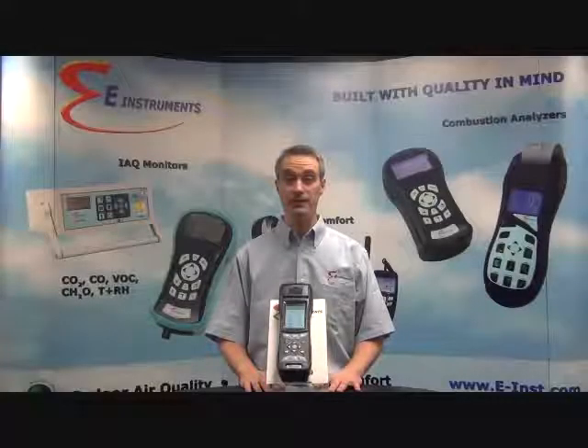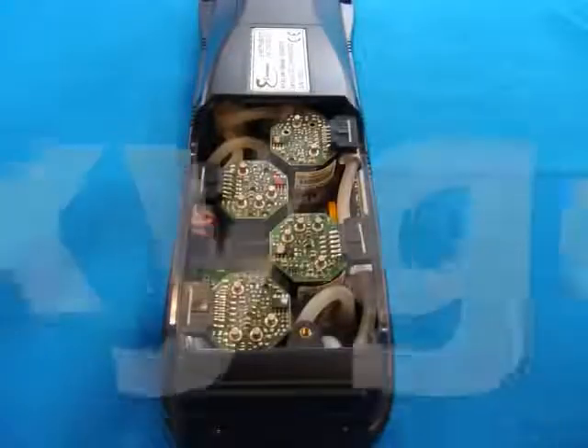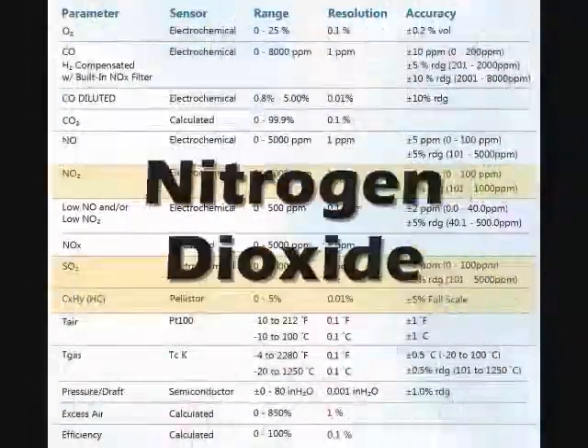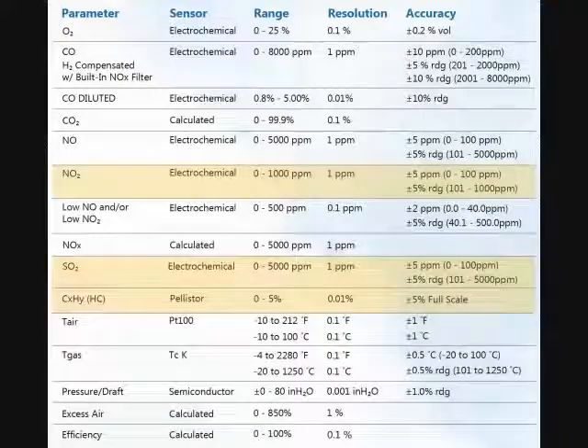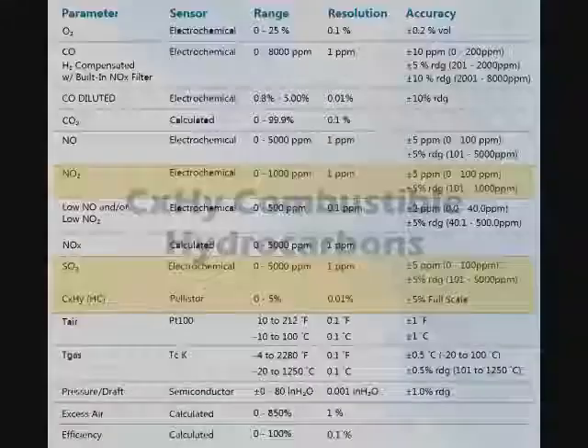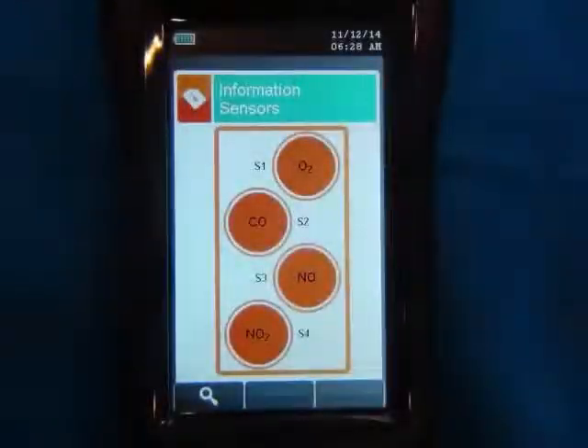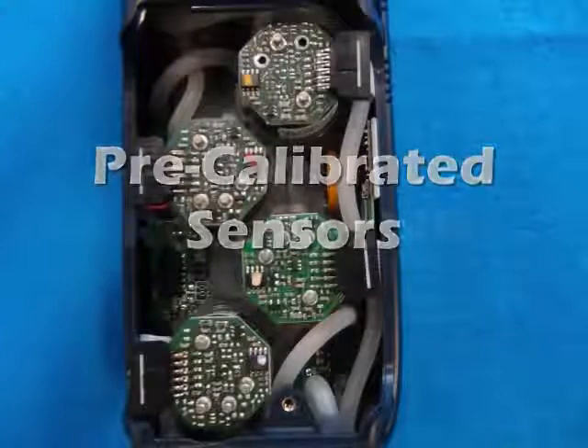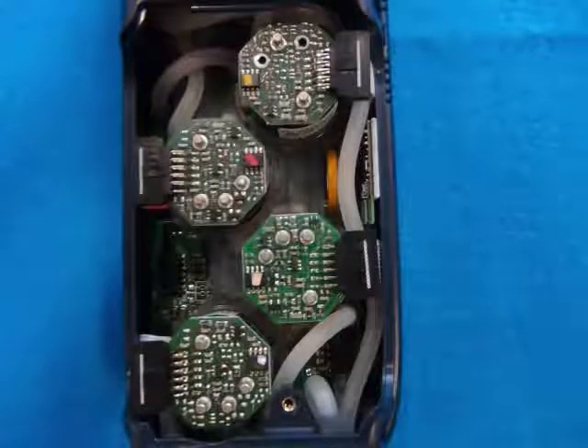The E-4500 can be configured to have a maximum of four gas sensors. The first three gas sensors are typically oxygen, CO, and NO for NOx. If a fourth gas sensor is required, the sensor options are NO2 for a total NOx measurement, SO2 for SOx, and CXHY combustible hydrocarbons. The fourth gas sensor can be installed when the E-4500 is first purchased or added as an upgrade at a later time. The gas sensors are pre-calibrated and easily field-replaceable, which minimizes analyzer downtime.